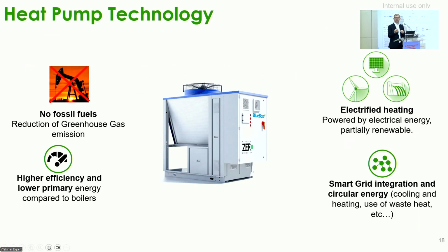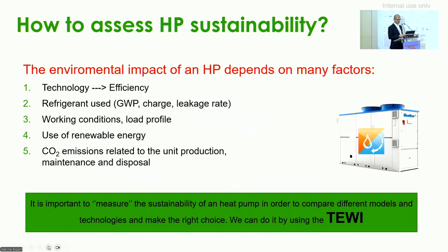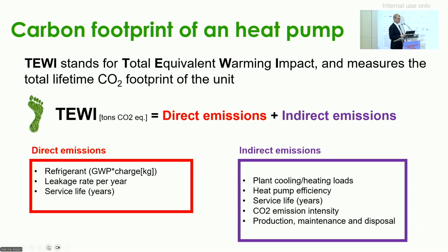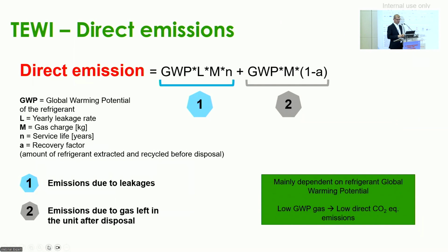It means that in some countries heat pumps receive incentives if they are controlled by the grid and operated in response to price signals depending on the status of the grid. Heat pumps can be compared from a sustainability point of view in an objective way using an index called TEWI, which stands for total equivalent warming impact. TEWI is made of direct emissions and indirect emissions. Direct emissions are made of two components, one linked to the yearly leakage rate and one depending on the recovery factor.